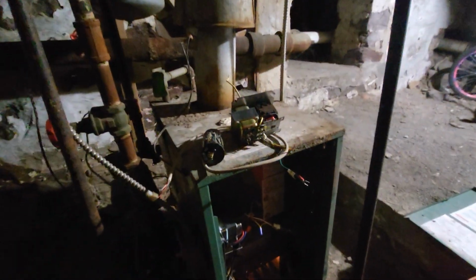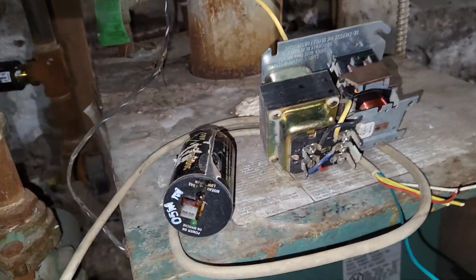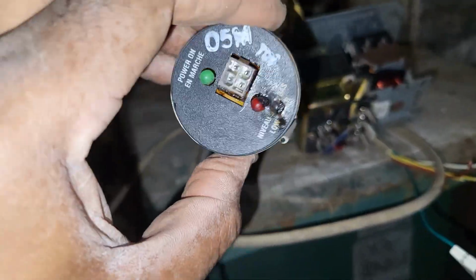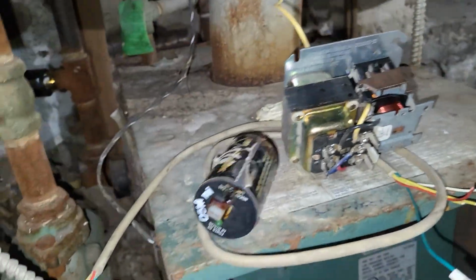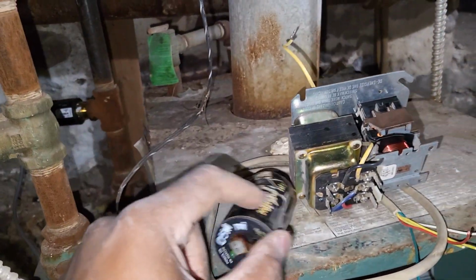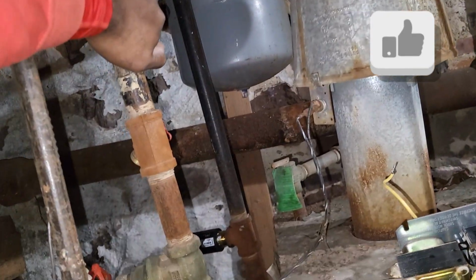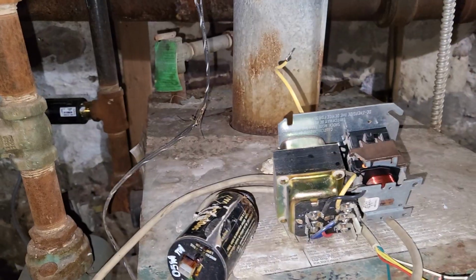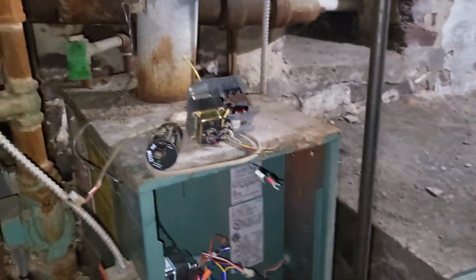But there you have it, guys. No heat call, gas boiler. Found the transformer open. Upon further investigation, we found why the transformer opened, and we recommend replacing the low water cutoffs and the fan center, and customer has heat. There you have it. He has 2 other boilers. Knock on wood, he said the other 2 are working, but we're going to recommend maintenance here next fall. But in the meantime, we're going to light a match, and we'll see this customer on the next one. Peace out, guys. I got to roll.